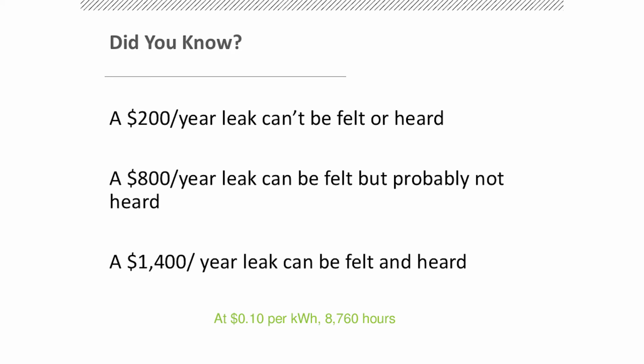So, did you know, at $200 a year, a leak can't be felt or heard. If you can feel it, it's $800 a leak, but it probably can't be heard. If you're hearing that leak, it's at least $1,400 a year. And that's at 10 cents a kilowatt hour, running around the clock. So when you go in and actually hear it, you can put dollar signs towards it. Many people say, well, geez, if I can't hear it, how am I going to fix it?